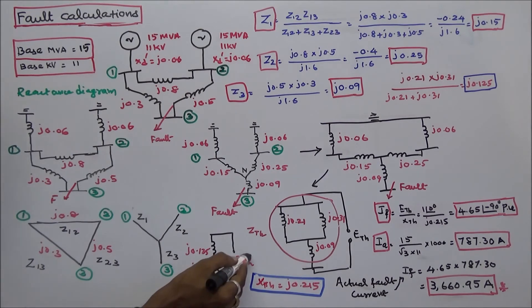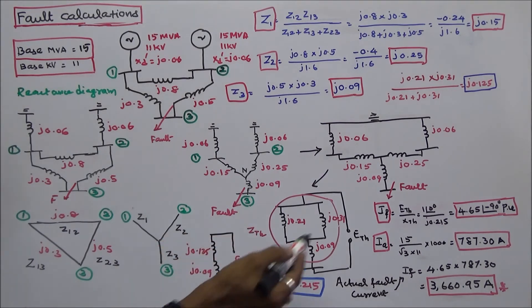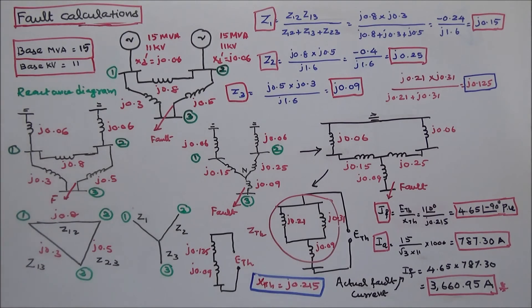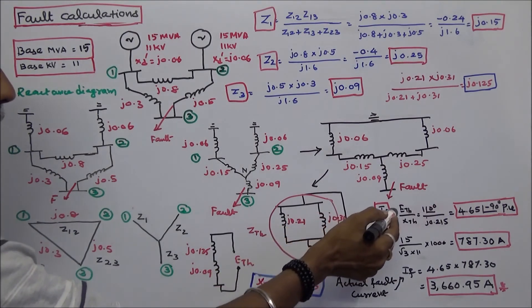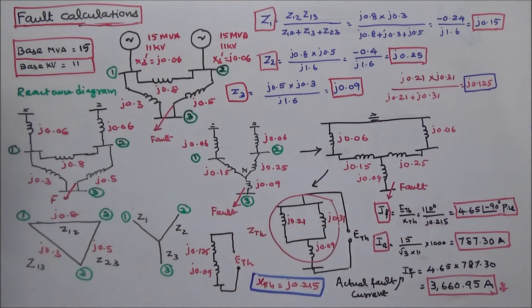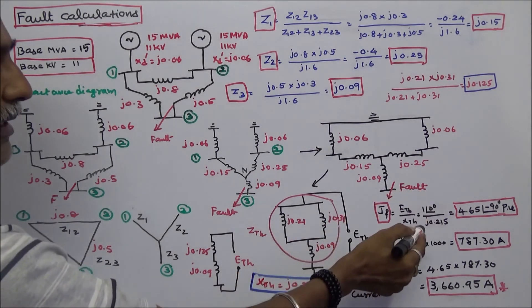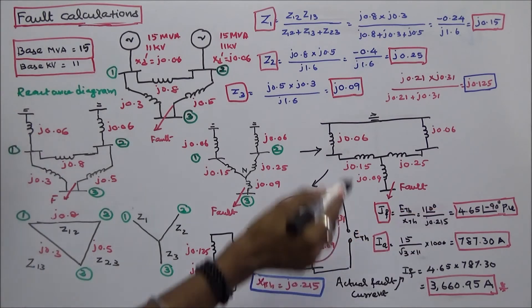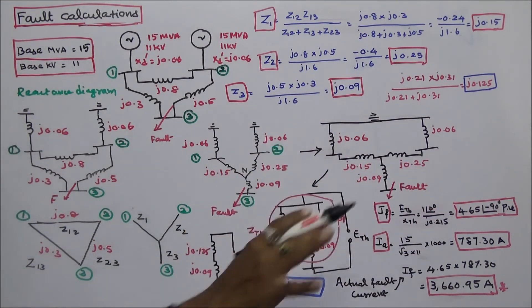The pre-fault voltage, which is the Thevenin equivalent voltage, is 1 angle 0 per unit. The per unit fault current IF is equal to the pre-fault voltage divided by the Thevenin reactance: 1 angle 0 divided by J0.215, which equals 4.65 angle minus 90 degrees in per unit.